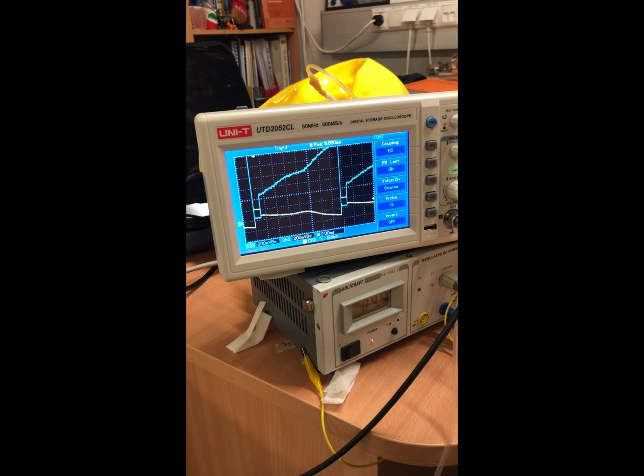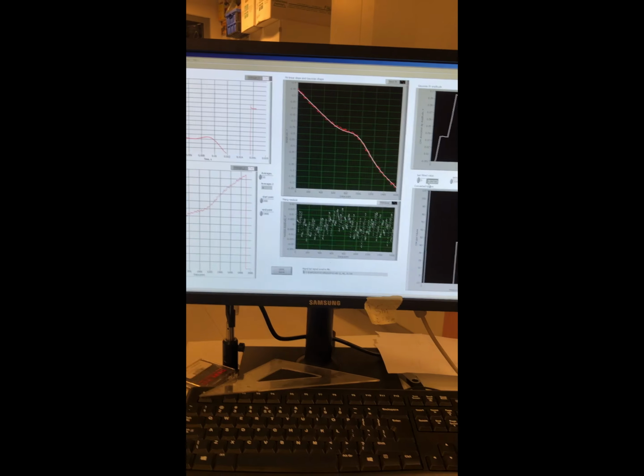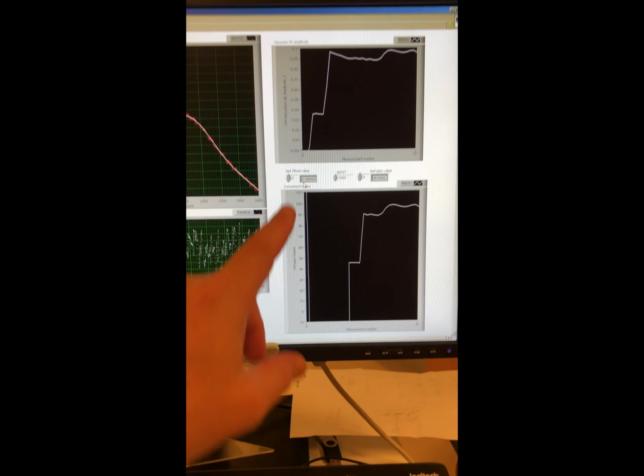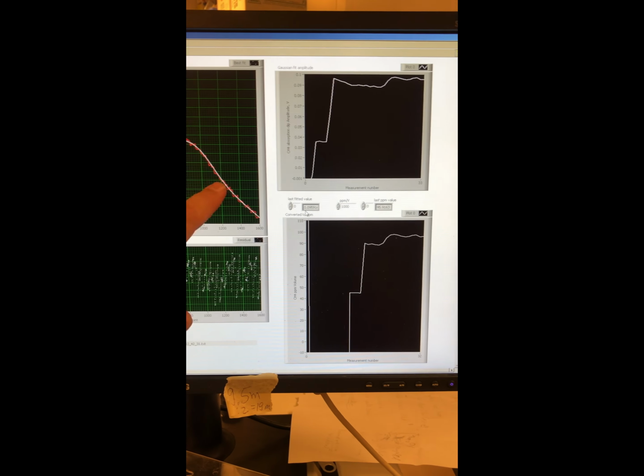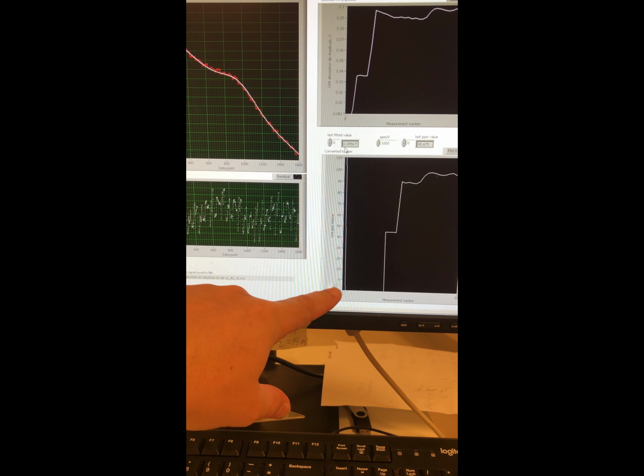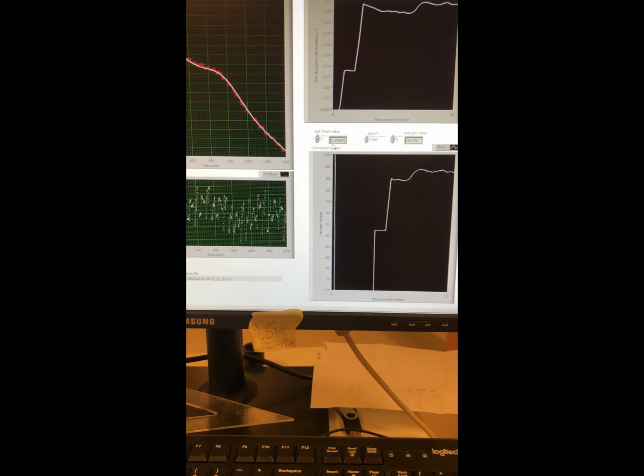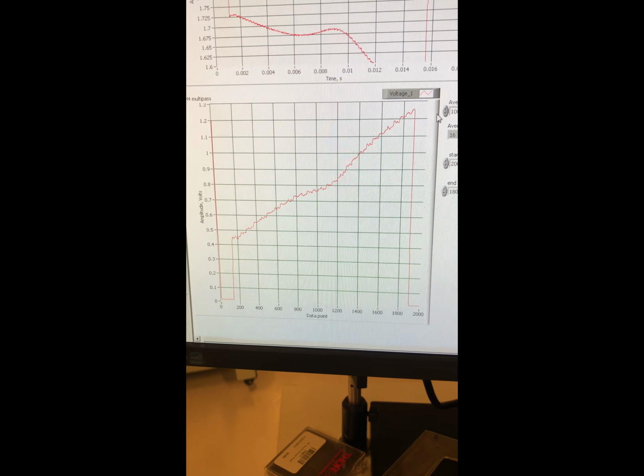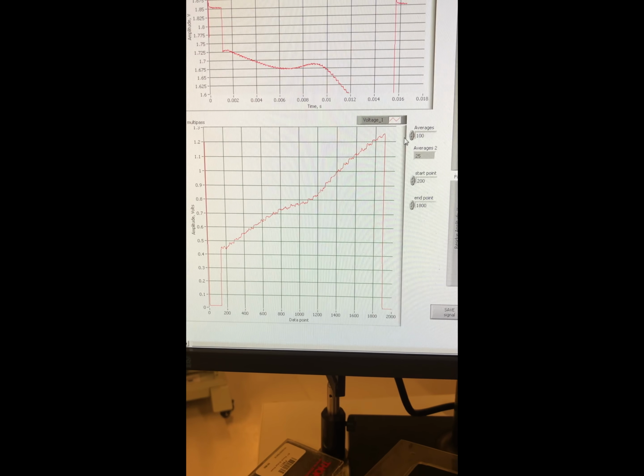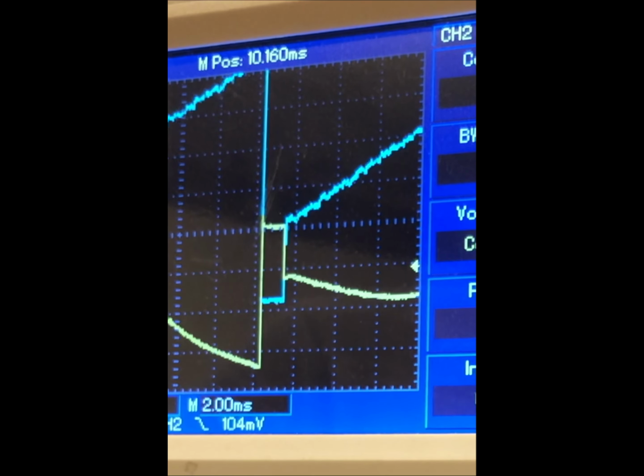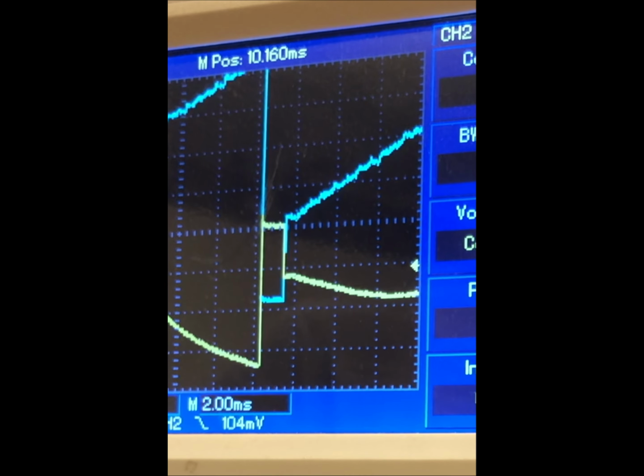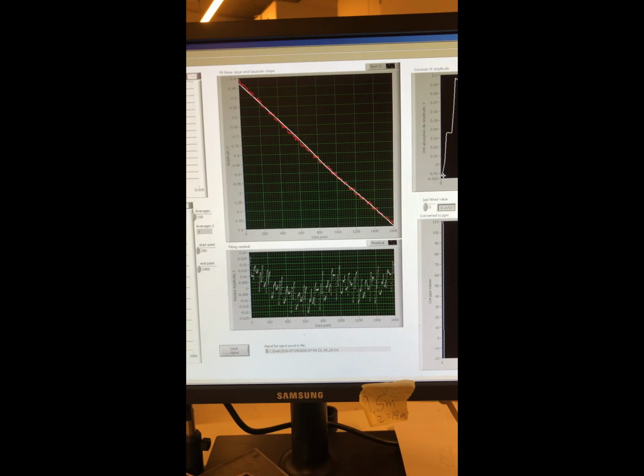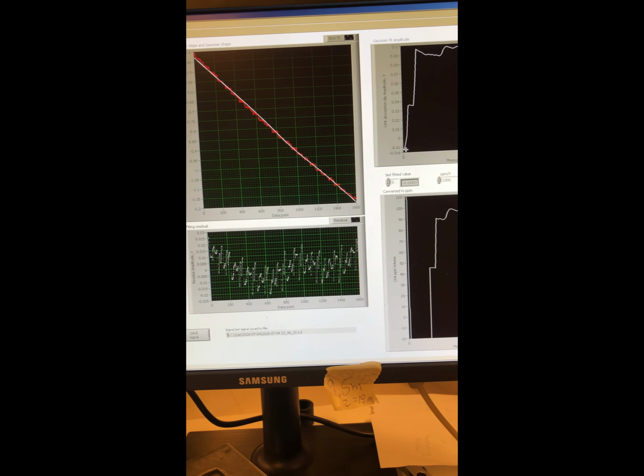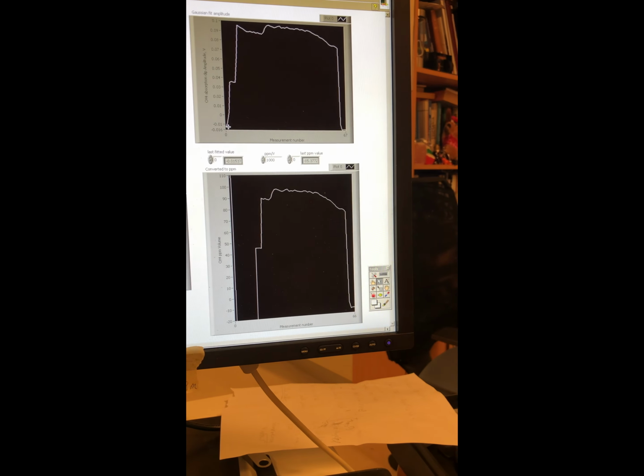Now after photodiode preamplifier, 100 ppm from the yellow bag, and 0.1 volt is the absorption line, and then I calibrate. Calibration constant 1000 ppm per volt. If it's more than half volt, that should probably be enough for the fringes on the scope screen to move a little bit. Then I apply air pump. After blowing in clean air, we do not get 0, but we get -16.